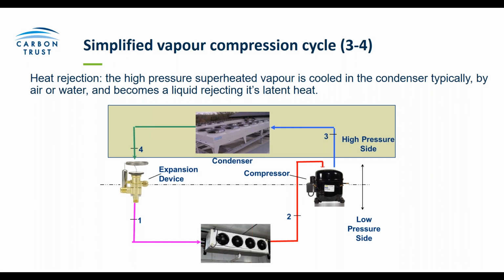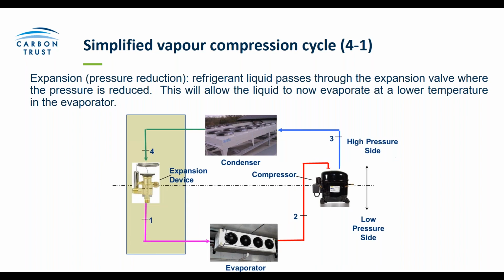So the latent heat is rejected by the system, and usually there's an ambient temperature which helps reduce the energy need here. So usually it's cooled by air or water in this part, but there are lots of different ways that the cooling can take place. Once the heat has been rejected, the refrigerant becomes once more a liquid, passes through to an expansion device, usually a valve, and this valve will essentially bring the pressure down, and liquid passes back to the evaporator to be used again in the system.